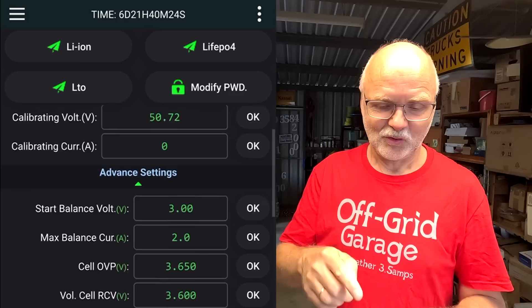It will come. But say for now your battery is new and you click on the lithium iron phosphate profile, bang, it resets everything to factory default. You can see the battery capacity has reset. This is obviously the 304 ampere hour. All the other settings are resetting to factory default.